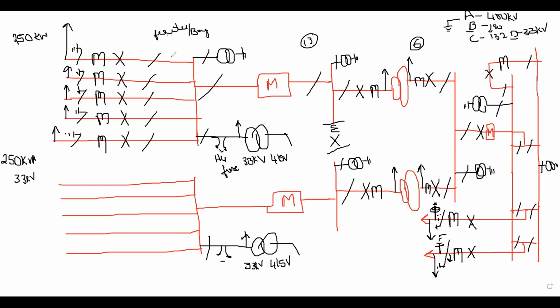Okay, team. Now I am giving the designation to each one. First of all, I am giving a number to each feeder. I am calling it feeder 1, feeder 2, feeder 3, feeder 4, feeder 5, feeder 6, feeder 7, feeder 8, feeder 9, feeder 10, 11, 12, 13. So this is the lightning arrestor, LA, isolator, what I told, 89 isolator, CT, breaker 52 and again 89, and the earth switch 57. Now this is 33 kV, so I am giving the letter D. What feeder? 1. So D1 lightning arrestor, D1 89A, D1 57, D1 CT, D1 52, D1 89.